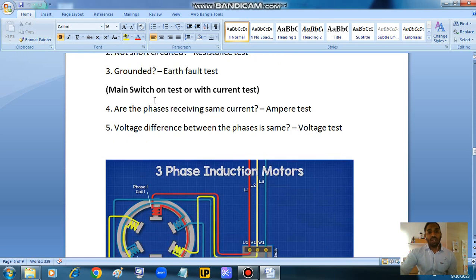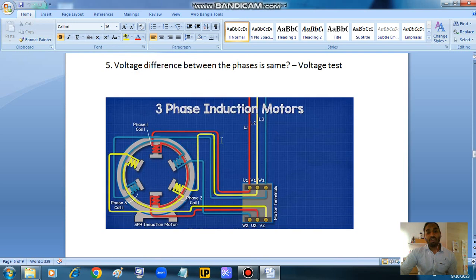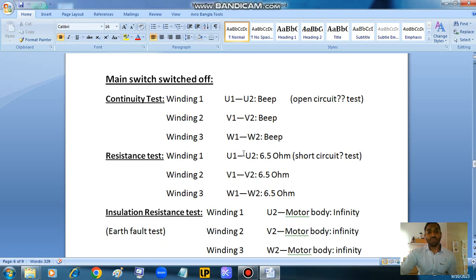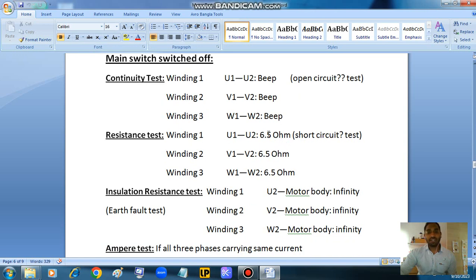The other two tests are the supply current test and the voltage test. The motor has to be powered, the main switch switched on, and we test with a clamp meter or ampere meter that all three lines L1, L2 and L3 are getting the same amount of current. They're consuming the same current, and the voltage differences between the phases are the same. Here we can see I have a video also. Next you can see U1 U2, V1 V2, W1 W2. A beep sound means there is continuity in the circuit, no wires are broken. Then for the short circuit fault test, the resistances are all the same, there is no abnormality.